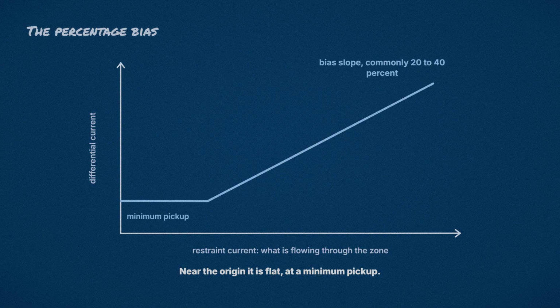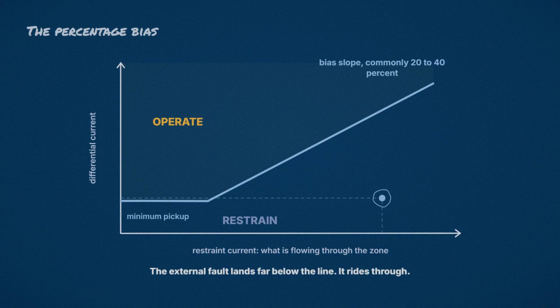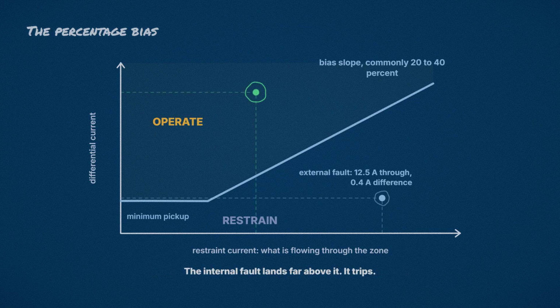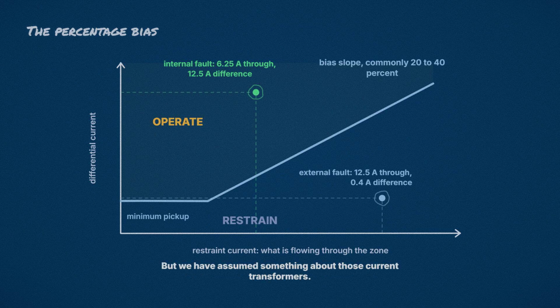Now put our two faults on that graph. The external fault sat at 12.5 amps of through current, with less than half an amp of difference, far below the line, so it rides straight through. The internal fault sat at half that through current, with 12.5 amps of difference, far above the line, so it trips. But we have quietly assumed something about those current transformers.